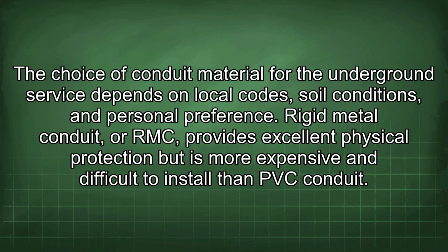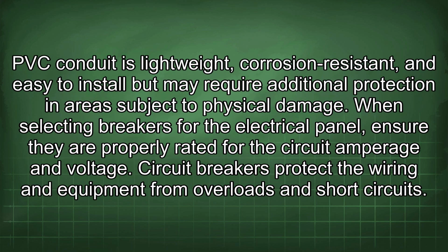The choice of conduit material for the underground service depends on local codes, soil conditions, and personal preference. Rigid metal conduit, or RMC, provides excellent physical protection but is more expensive and difficult to install than PVC conduit. PVC conduit is lightweight, corrosion resistant, and easy to install but may require additional protection in areas subject to physical damage.